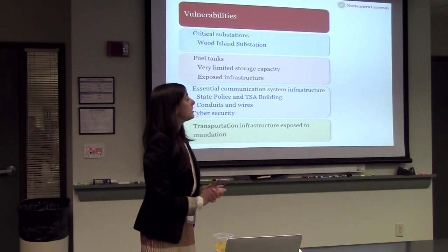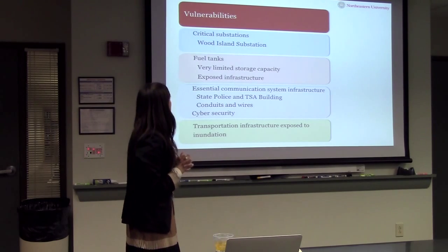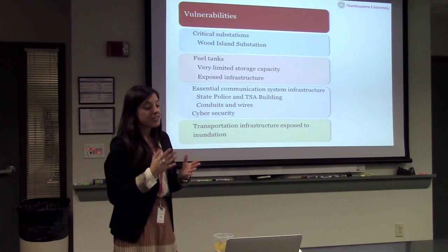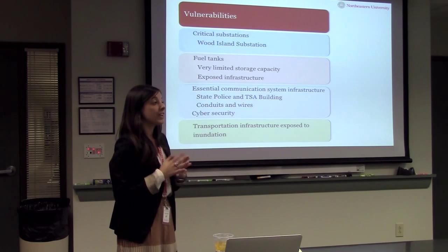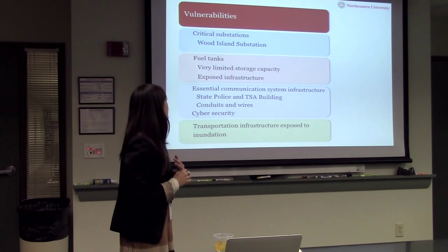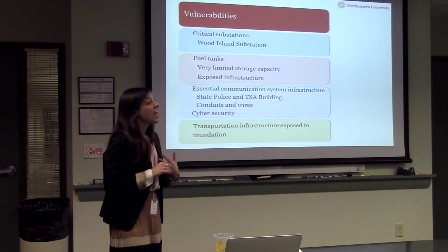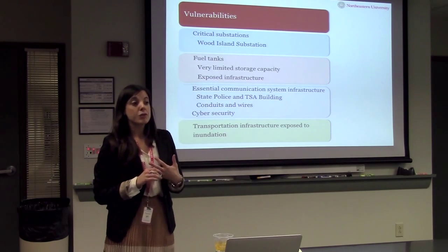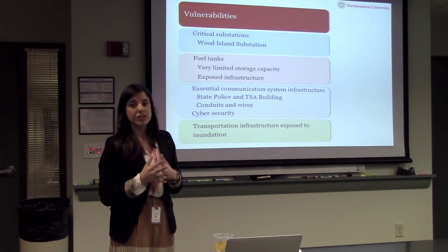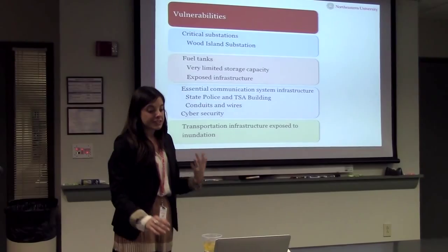During our research, our field trip, and our conversations with Logan, we have identified main vulnerabilities at the airport. In general, they are associated with flooding and vulnerabilities in electrical infrastructure such as substations, communication systems, and the transportation infrastructure. We have also identified vulnerabilities in the fuel system, very short fuel storage, and that the infrastructure is exposed to accidents, man-made hazards, and cyber security issues.